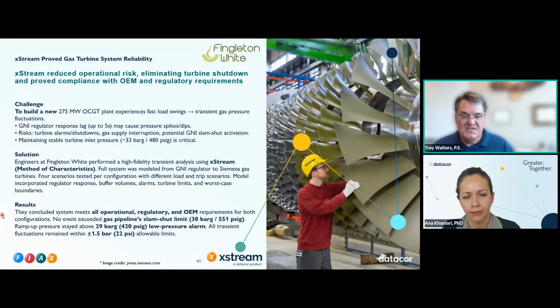And results, they concluded the system met all operational, regulatory, and OEM requirements for both configurations, both the 5 and the potential 7 turbines down the road. No event exceeded the gas pipeline slam shut limit. Ramp up pressure stayed within the 29 bar low pressure limit, and all transient fluctuations remained within the 1.5 bar allowable limits.